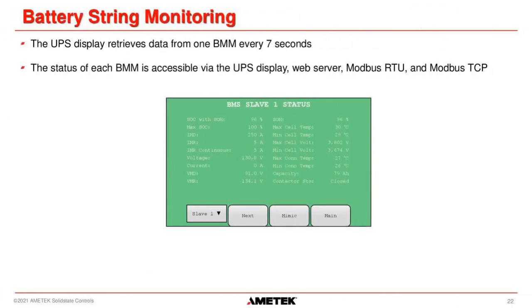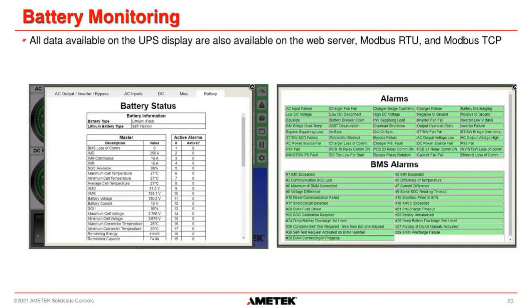As I said, you can retrieve data from each battery string every 7 seconds, or a string is each cabinet. The status of each BMM is accessible via the UPS display, web server, Modbus RTU, and Modbus TCP. Here are some screenshots of the battery status, the battery voltages, currents, and you can see if there are any active alarms. The bottom half of the picture on the right, everything is in green right now in this screenshot, but if an alarm activates, it'll turn red.